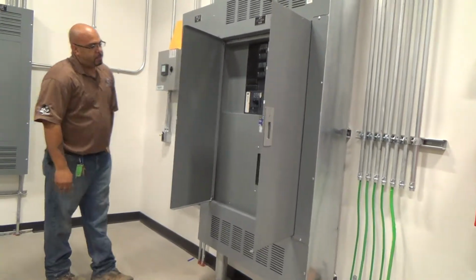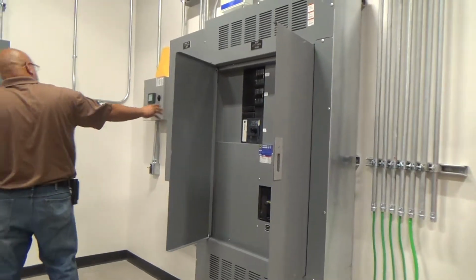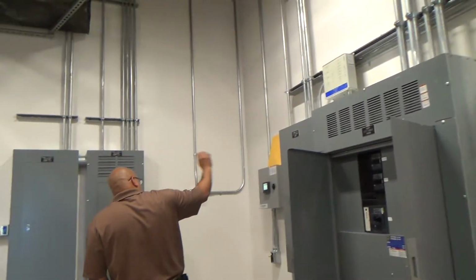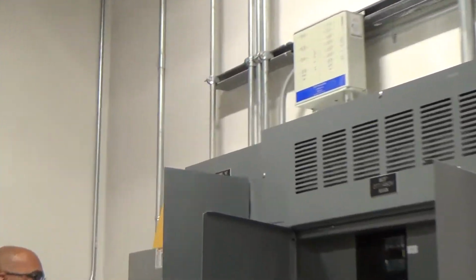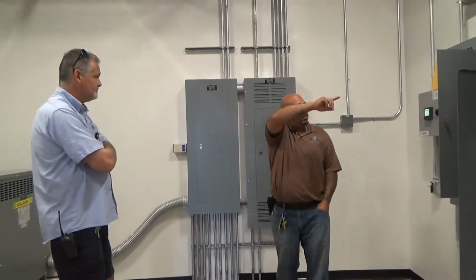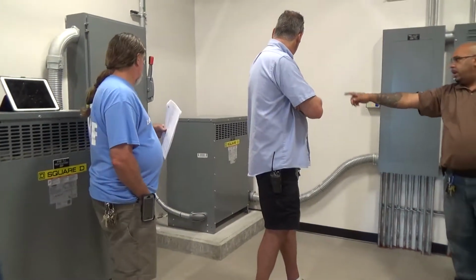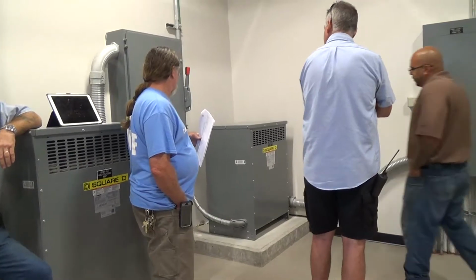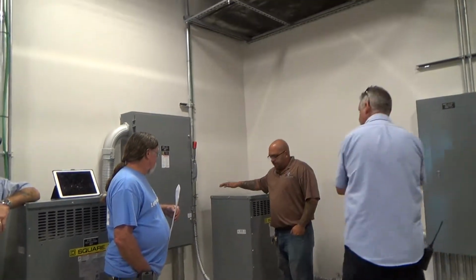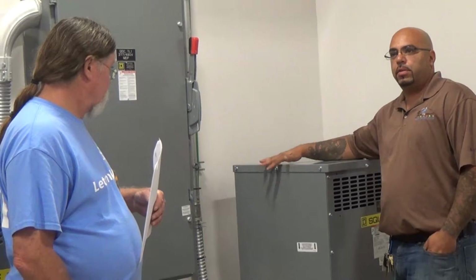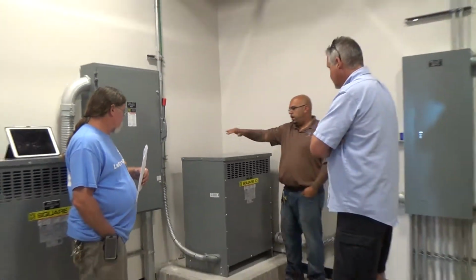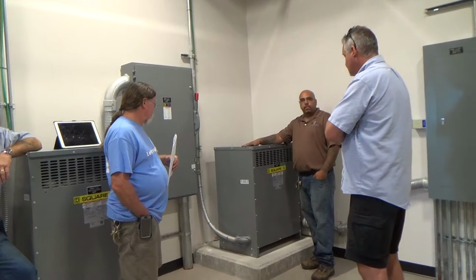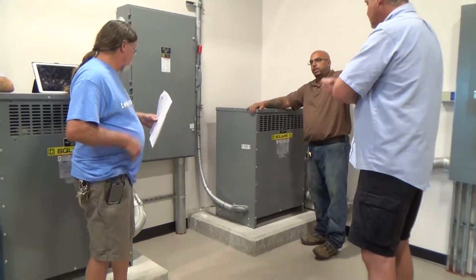This is the main distribution panel. It feeds all of your equipment, starting from a high voltage panel in here, which is for the most part lighting and some air handlers, and then you go into low voltage panels. Low voltage panels get fed from the MDP into a transformer and then hit the switch. So if the low voltage panel is in this electrical room, it just comes from the MDP to the transformer because the means of disconnect is within sight in the same room.